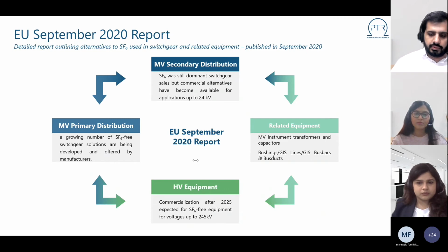The Commission was of the view that after full market deployment, only marginal additional cost would be expected, because the designs of alternatives were very similar to products that use SF6. Full commercialization of the alternative solution was expected by 2023. Lastly, breaking was not an issue in primary distribution, as vacuum circuit breakers were already common by 2020.